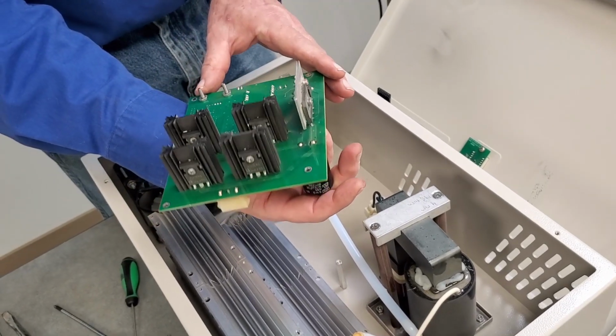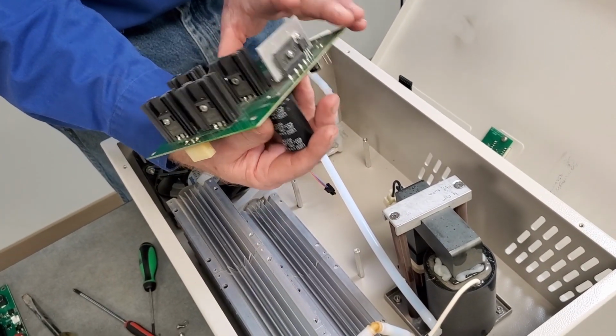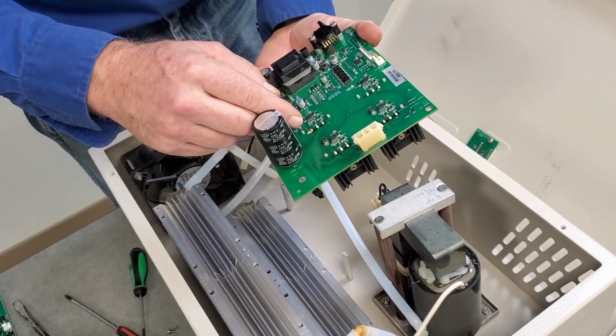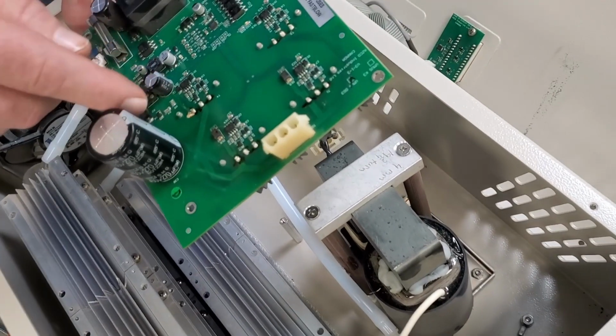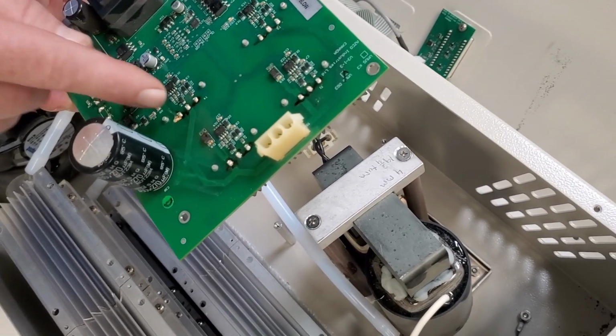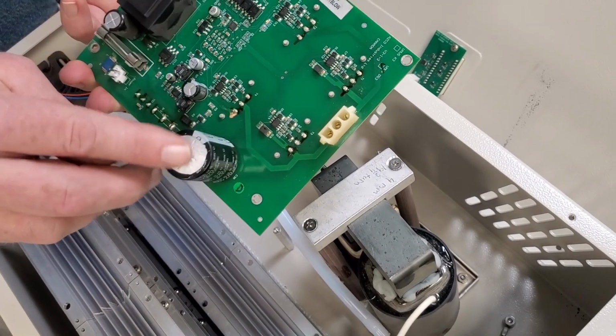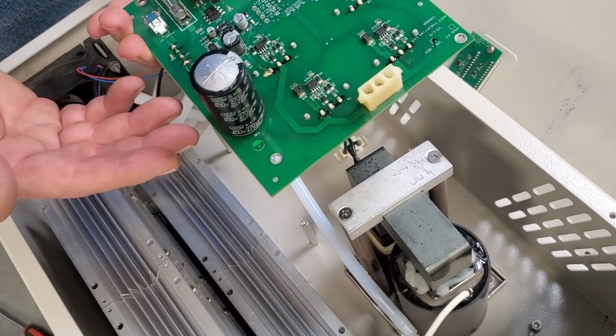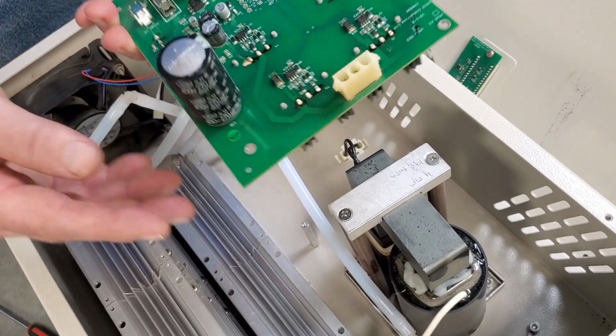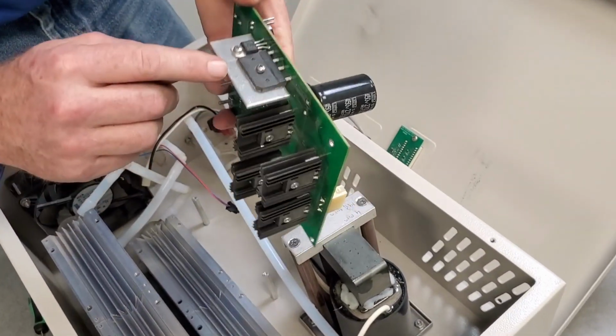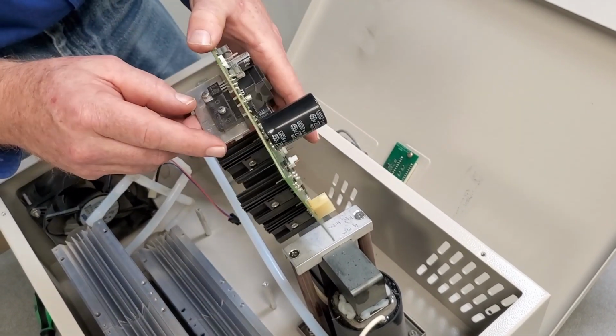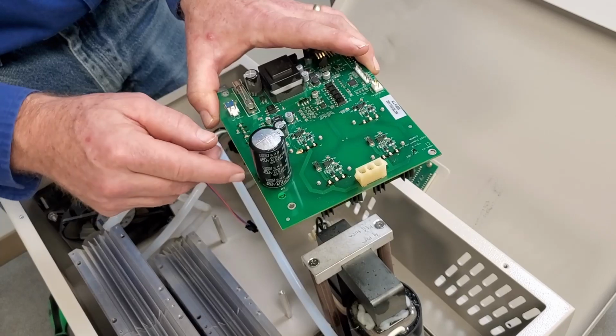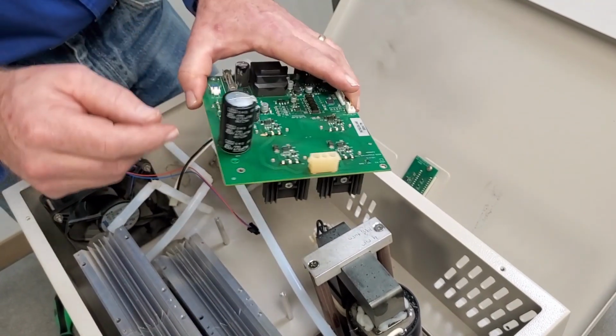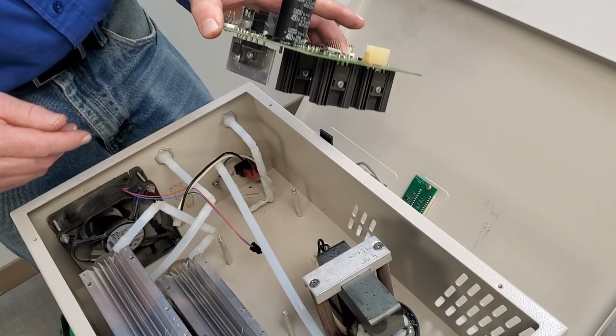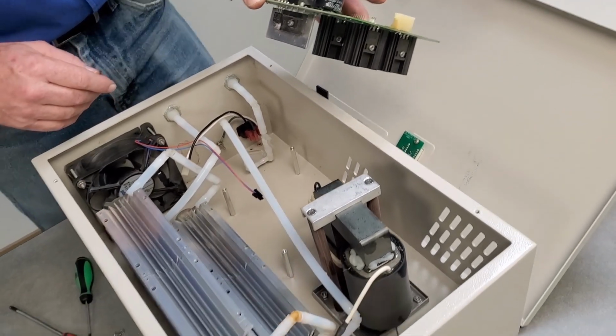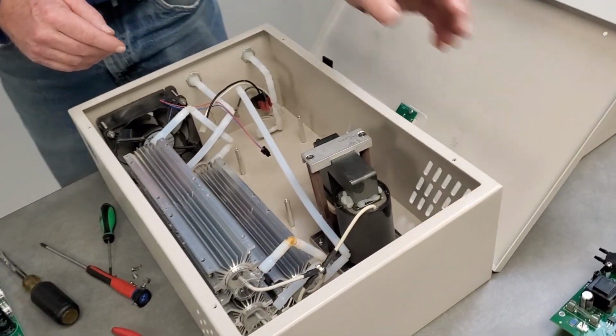This board isn't showing too much indication of problems other than the black. You can just see that things got really hot in here, and some of the flux there is melting off, and this capacitor is bulged up a little bit as well, but when running it doesn't do anything. You can see also here, these are the transistors that are switching the signal that may have gotten overheated. This board needs to be replaced. The fact that this is discolored, all these are clues that it just got too hot in here. So I'm going to replace that board.